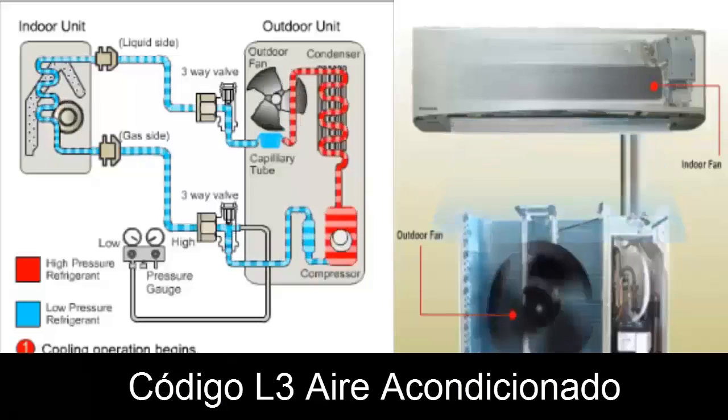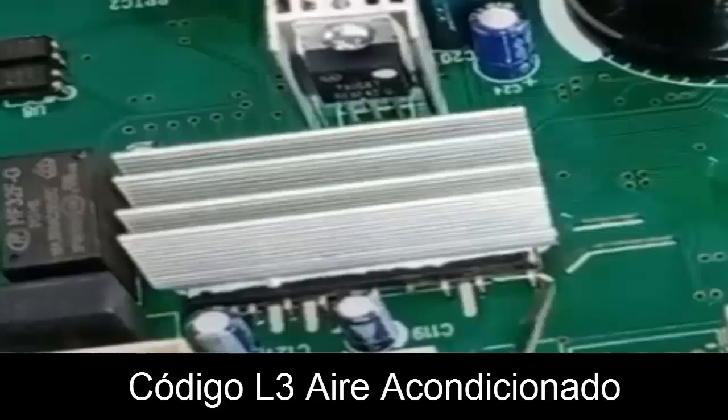5. Check the IPM screws. Ensure that the screws fixing the IPM and the heat sink are properly installed. A poorly installed heat sink can cause overheating and failures in the IPM.